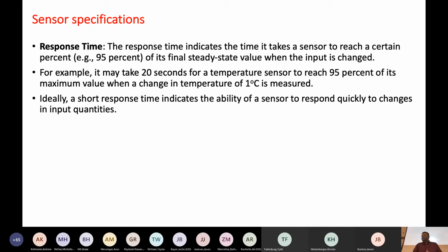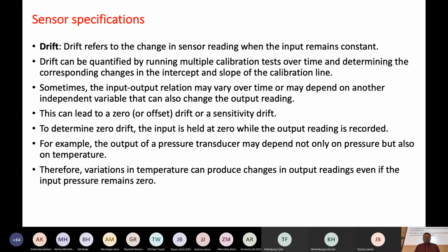That response time is important because it allows fast detections. You don't have to wait a long time. Imagine if a glucose sensor took 2 hours to respond. For those 2 hours, the person can't do anything. They can't eat, they can't decide what kind of medication or insulin they need to take. So you want very quick response times, meaning the sensors respond quickly to whatever changes they're exposed to. That's a very important parameter.